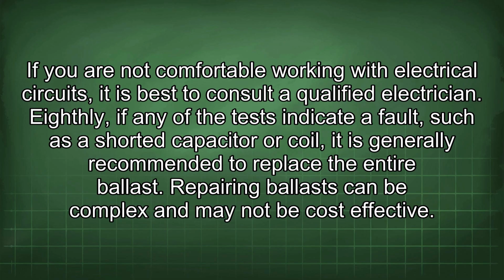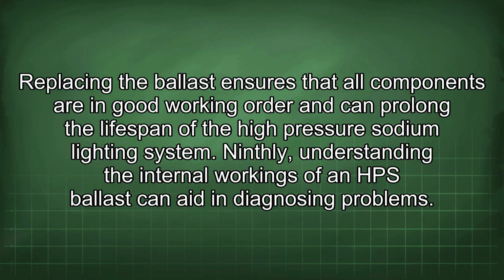Eighthly, if any of the tests indicate a fault, such as a shorted capacitor or coil, it is generally recommended to replace the entire ballast. Repairing a ballast can be complex and may not be cost-effective. Replacing the ballast ensures that all components are in good working order and can prolong the lifespan of the high-pressure sodium lighting system.